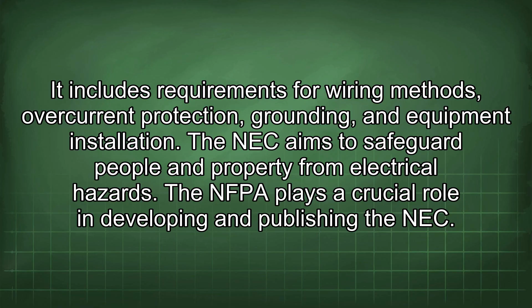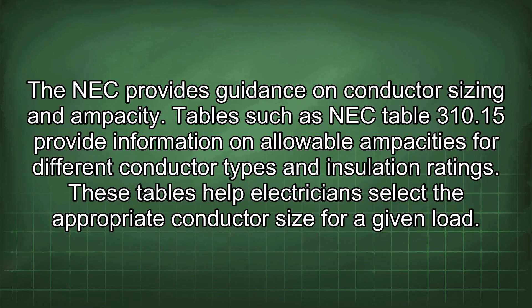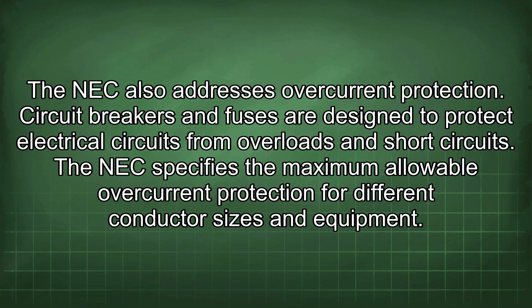The NEC provides guidance on conductor sizing and ampacity. Tables such as NEC Table 310.15 provide information on allowable ampacities for different conductor types and insulation ratings. These tables help electricians select the appropriate conductor size for a given load. The NEC also addresses overcurrent protection. Circuit breakers and fuses are designed to protect electrical circuits from overloads and short circuits. The NEC specifies the maximum allowable overcurrent protection for different conductor sizes and equipment.